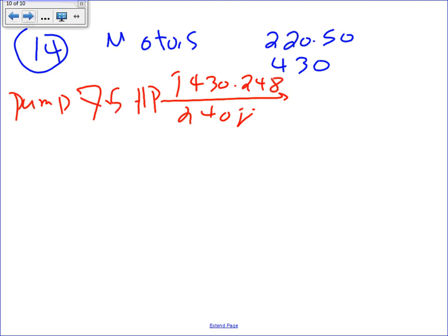What's the full load current of that 7.5 horsepower from the table? Did we have the right table? 430.248. Yep. 7.5 horsepower, 40. Okay. So the full load amp is 40 amps. That's how we calculate the volt amp of the pump. Only one pump for the swimming pool that they have there. They don't have 30 of them. Only one pump here, just for the whole apartment.